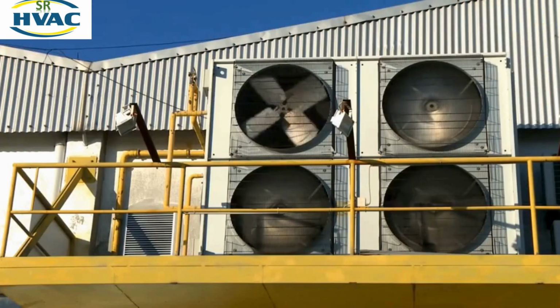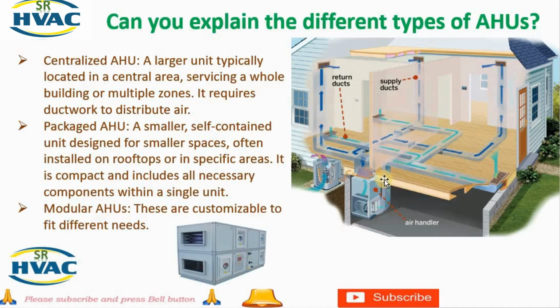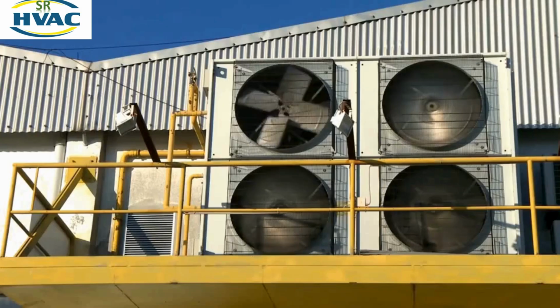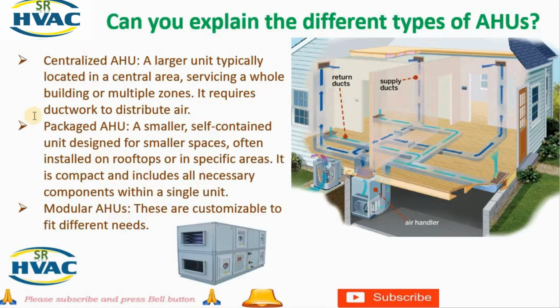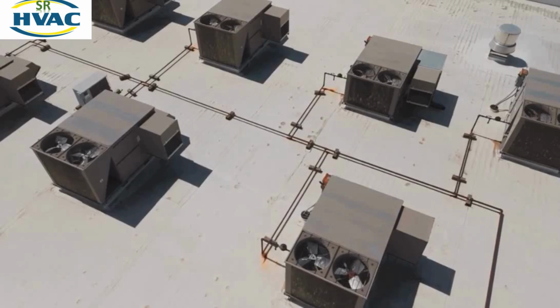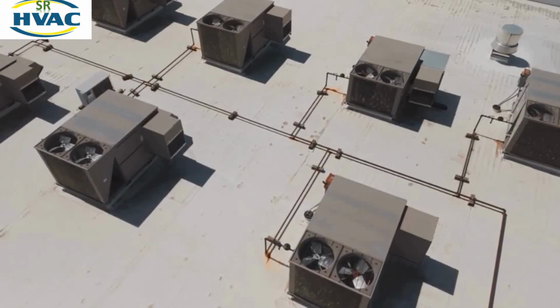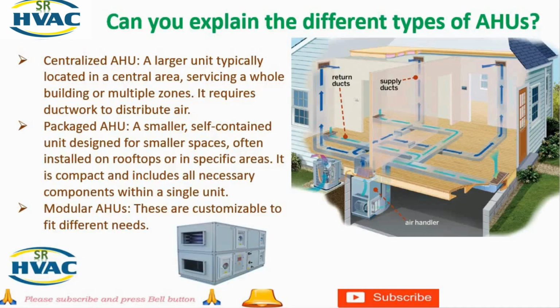Centralized AHU, a larger unit typically located in a central area, servicing a whole building or multiple zones. It requires ductwork to distribute air. Centralized AHUs are ideal for large buildings because they can efficiently manage air distribution and quality across multiple zones. Package AHU, a smaller self-contained unit designed for smaller spaces, often installed on rooftops or in specific areas. It includes all necessary components within a single unit. Modular AHUs. These are customizable to fit different needs.